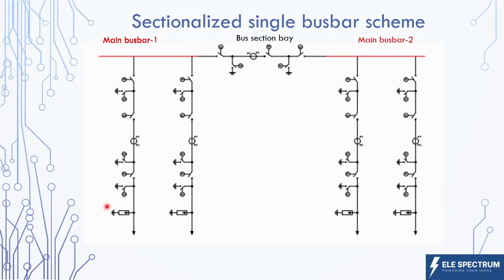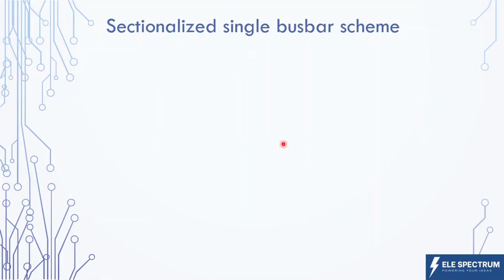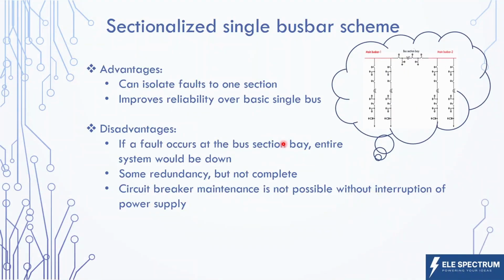So we have one set of feeders connected to this bus bar, another set of feeders connected to this bus bar, and these two sections can be connected with the bus section bay. And this is our sectionalized single bus bar scheme. So what are the advantages and disadvantages of this scheme? When we talk about advantages, we have one advantage over a single bus bar scheme: we have sectionalized this bus bar, so the fault is confined to only one section and we can still operate the other section by isolating it with the bus section bay.